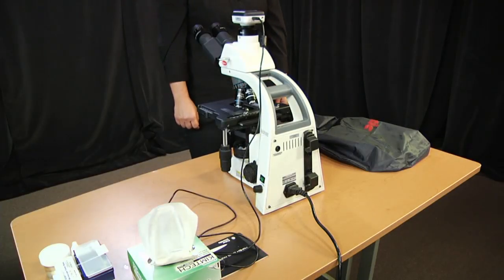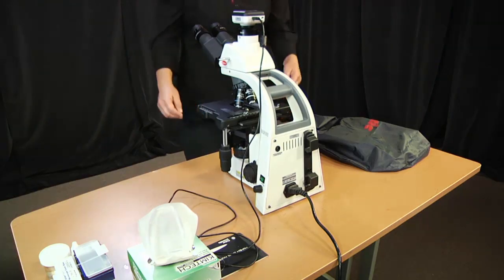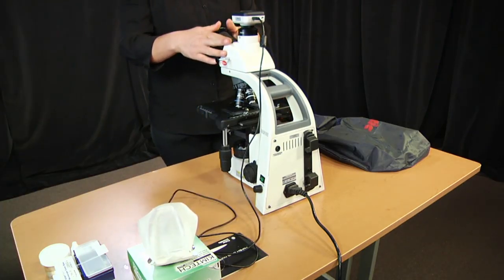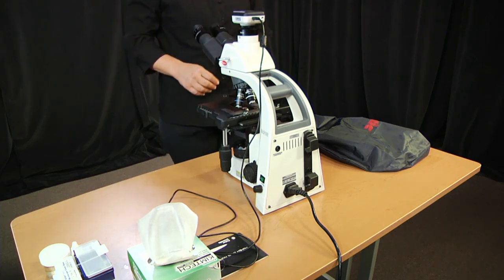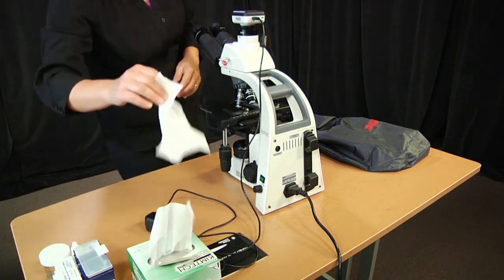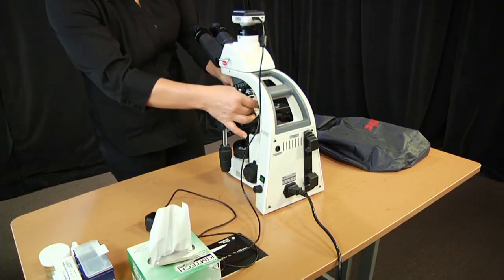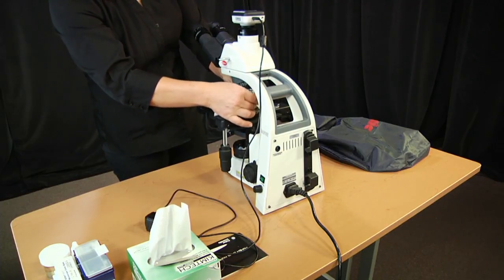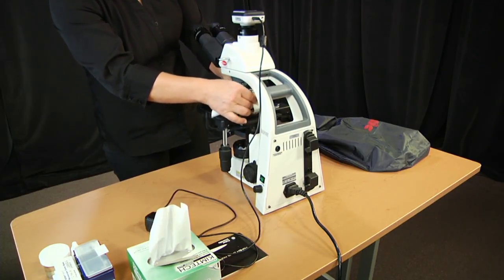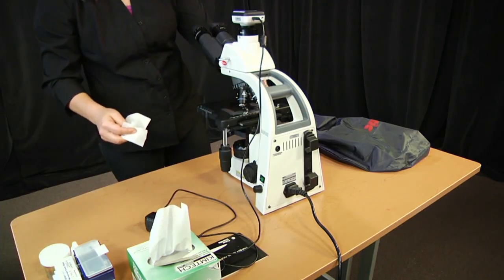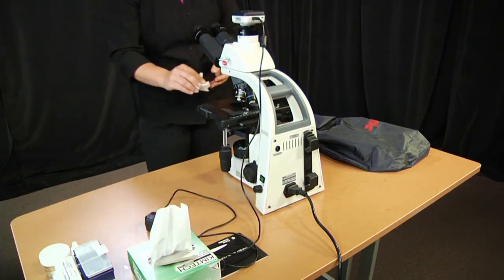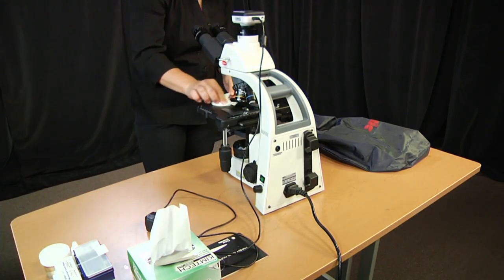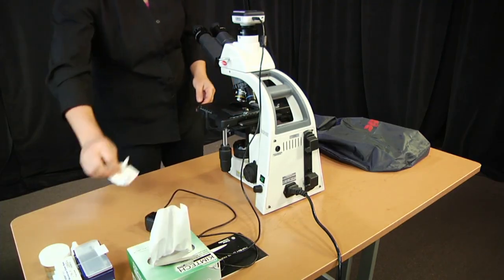Alright, to finish up this lesson on microscopy, make sure you clean up. Your microscopes are really valuable. This one is about $2,000. Other ones are up to $30,000, $50,000, $100,000. Make sure to take care of the equipment. Couple of simple steps. Make sure you clean off the 100x lens if you used oil. Again, don't get any oil ever on any of the other lenses. If there's any oil on your stage, just wipe over with a Kim wipe and clean it off.